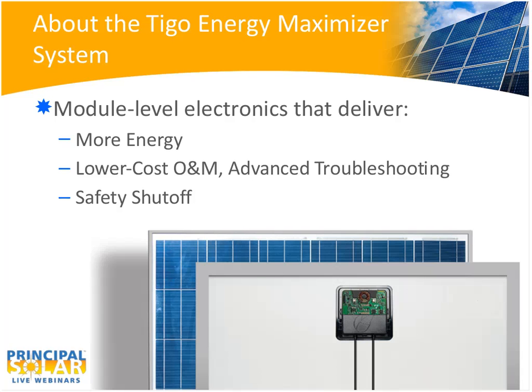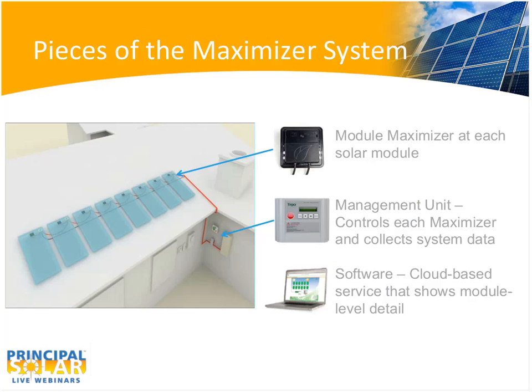And finally, we enable a safety shutoff mechanism, which I'll talk about at the end. Basically, it's a low-voltage shutoff, which is actually part of the code requirements for 2014. So we're ahead of the curve, as is Tigo, on offering a lot of the safety and anti-islanding benefits of a low-voltage shutoff that isn't mandated yet but will be mandated soon.